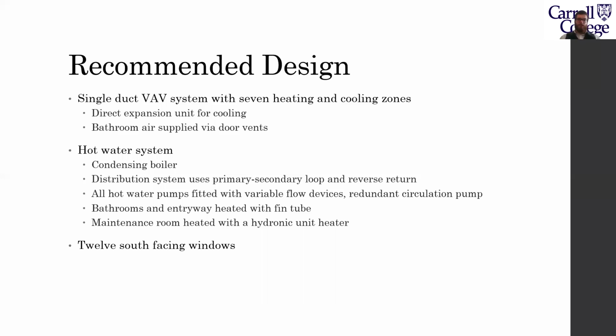The distribution system will use a primary, secondary loop, and reverse return. All the hot water pumps will be fitted with variable flow devices, and the circulation pump will have a redundant pump in case of failure. The bathrooms and the entryway will be heated with fin tube, and the maintenance room will be heated with a hydronic unit heater. I also decided to go with 12 south-facing windows for the increased daylighting.